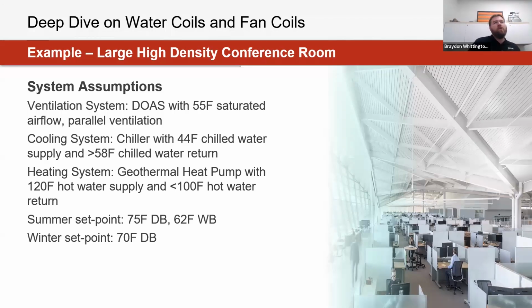So with this, having a chiller running around 45 or 44 degrees chilled water supply going through our system, and a geothermal heat pump within the system. So we're starting to work with that 120 entering water that can be paired nicely when looking at fan and blower coils, just as we have a bigger coil, and then some different set points as well. And this one's even a DOAS example of what you would see there too, Tom, just for this ventilation system for being able to provide with this product.